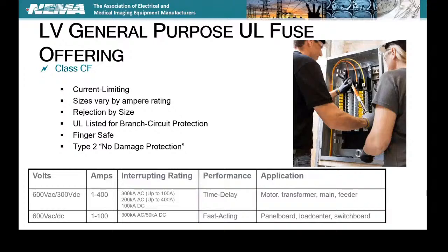Next slide. So CF, that's your cube fuse. This was an innovative solution out of the Bussmann group that basically took that Class J fuse characteristic and put it into another form factor so that you can make a smaller panel board type of deal. But it's basically a Class J fuse. The rejection is by size and those little blades. They go up to 100, actually 200 amps, I think now, or 400 amps, 600 volt AC up to 400 amps, up to 300,000 amp interrupting.